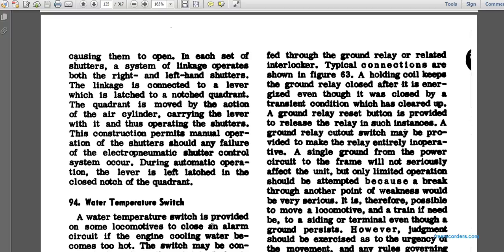A holding coil keeps the ground relay closed after it is energized, even if the grounding condition clears up. A ground relay reset button is provided to release the relay in such instances. A ground relay cutout switch may be provided to make the relay entirely inoperable. A single ground in the power circuit through the frame will not seriously affect the unit, and only limited operation should be attempted, because a breakage at another point of weakness would be very serious.